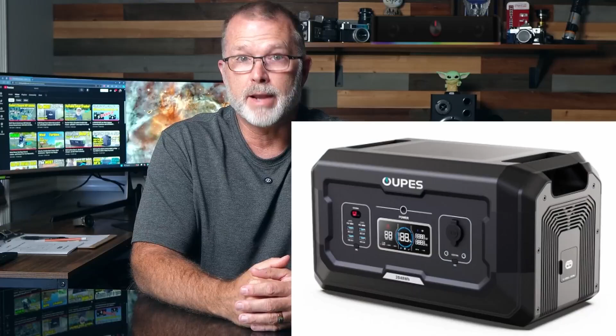Those B2 expansion battery modules not only have their own USB ports and 12 volt car socket outputs, but they also have a 12 volt 30 amp Anderson output connector and the ability to be independently charged via up to 2100 watts of solar, which means they're very capable DC power stations on their own, able to function completely independent of the main unit, whether it's a Mega 1, a Mega 2, or a Mega 3. Those B2 battery expansions are rated for 2,048 watt hours, so adding just one of those expansions to the Mega 1 will triple your overall battery capacity.